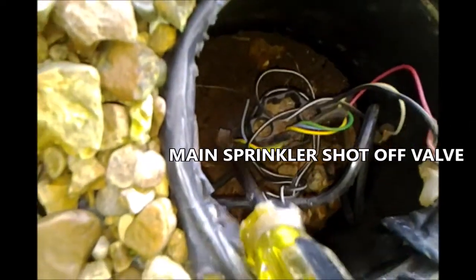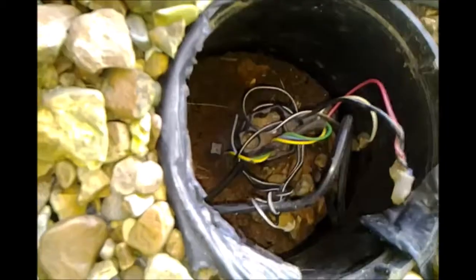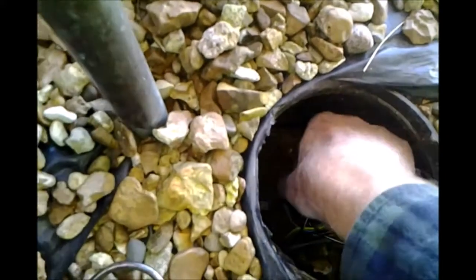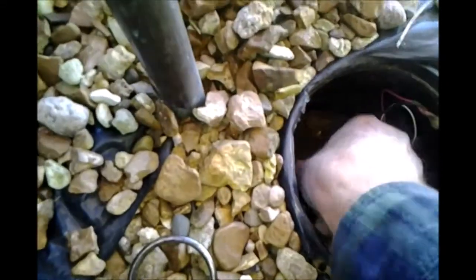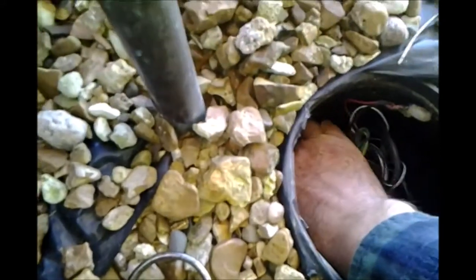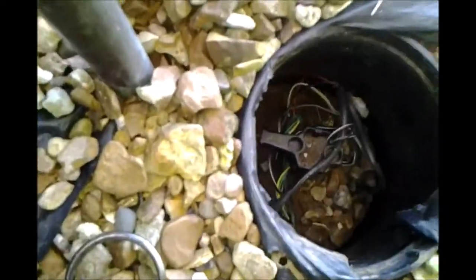Okay, to finish draining this pipe here, this is the discharge side that goes into the sprinklers. You open this little star screw here, and that drains water out of this pipe. I think you turn this valve to the left, counterclockwise, and if there's still water in this pipe, it'll come out there, I think, and it's not, so I think I've got this line drained, which is important because it's going to be above ground, and it's going to be the first thing to freeze.